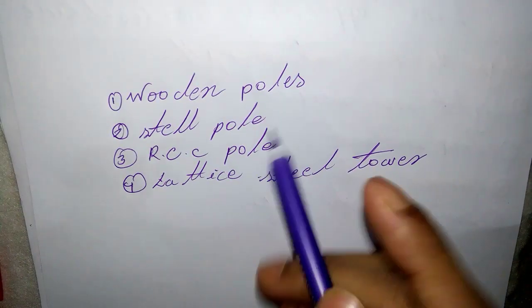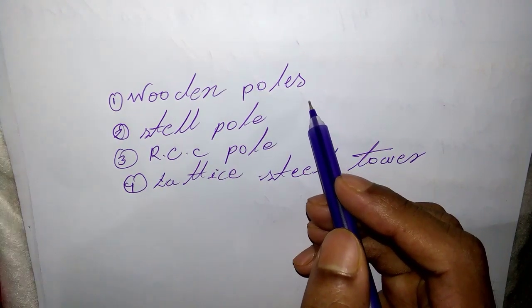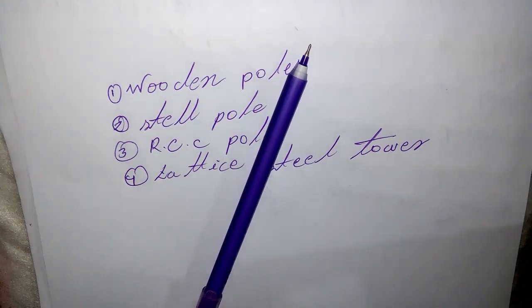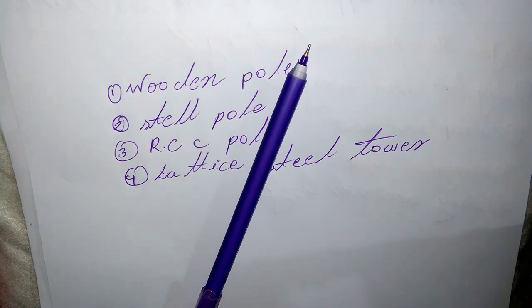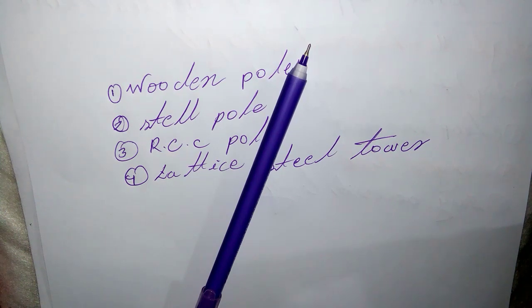Wooden poles are made of seasoned wood like sal and chir, and are suitable for lines of moderate cross-sectional area with relatively shorter spans, up to 50 meters. Such supports are cheap, easily available, and provide insulating properties, and are therefore widely used for distribution purposes.